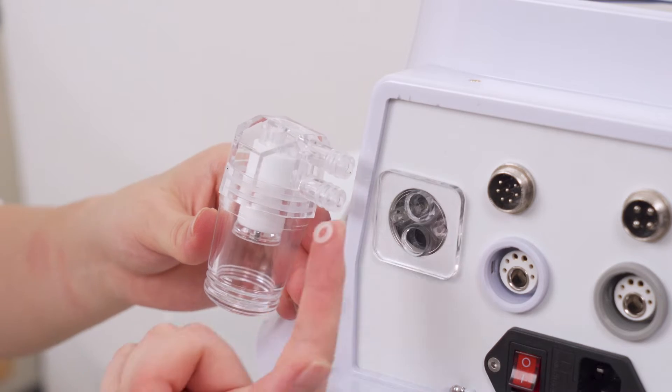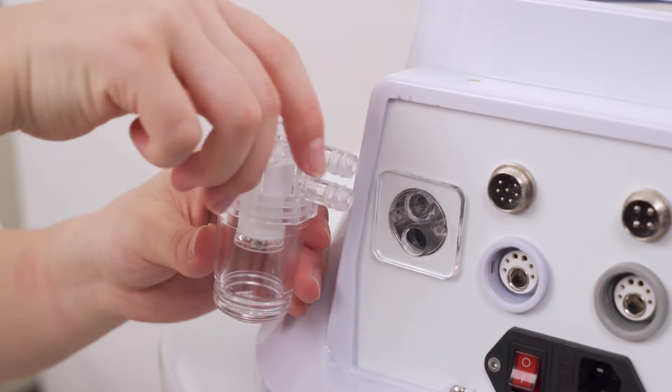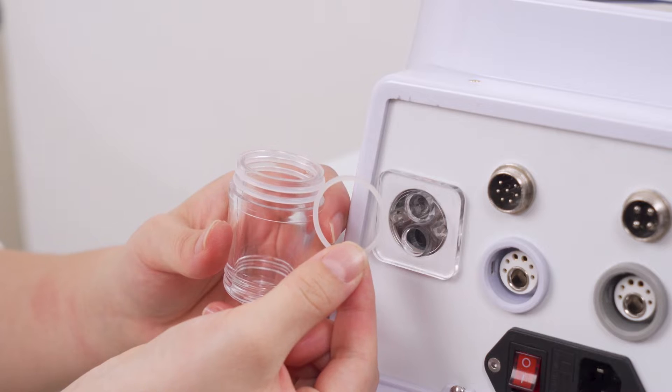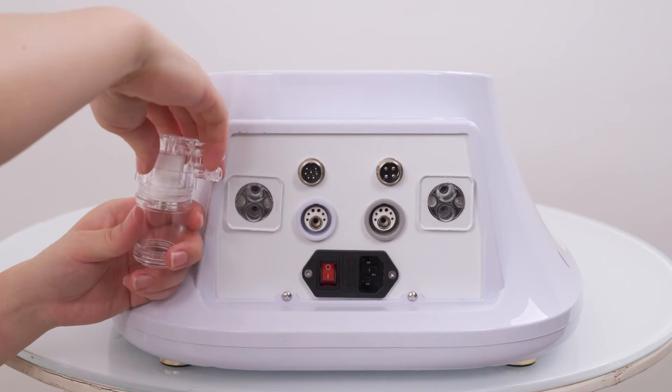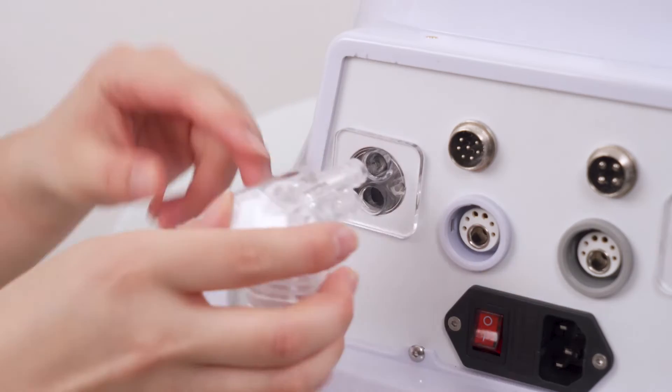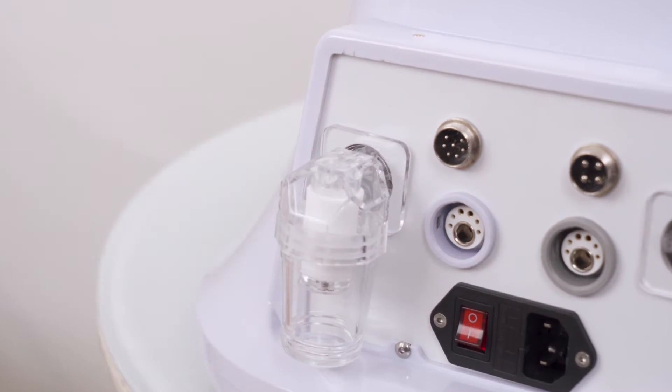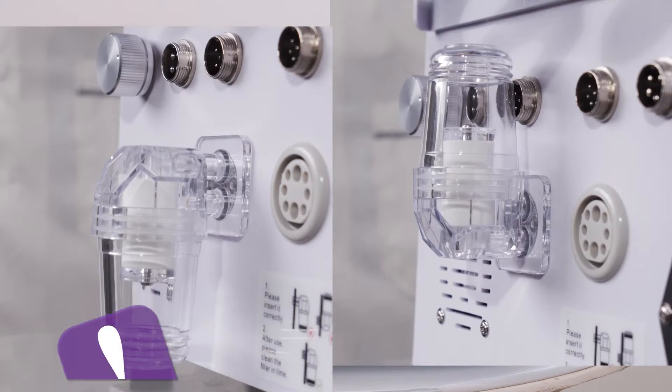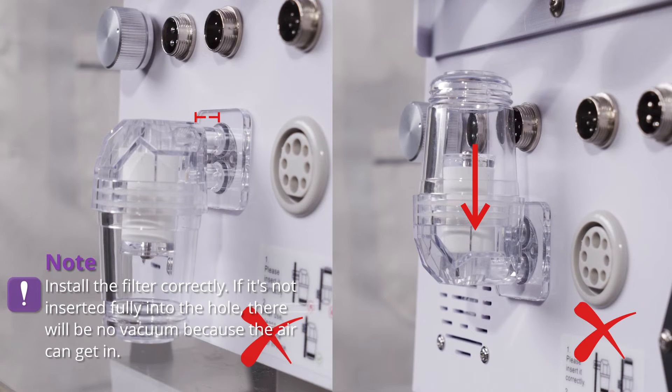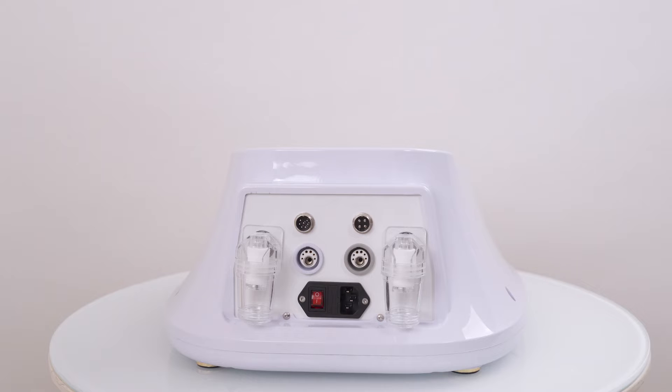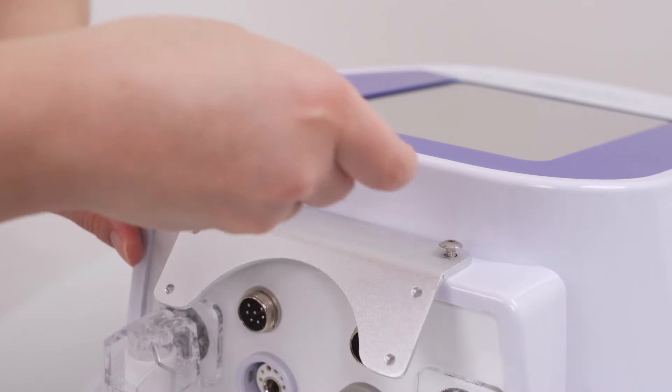Install the filter. There are four small rubber rings and two larger rubber rings on the filter which can be replaced with spare ones when necessary. Please note, install the filter correctly. If it is not inserted fully into the hole, air may get in and there will be no vacuum. Install the holder.